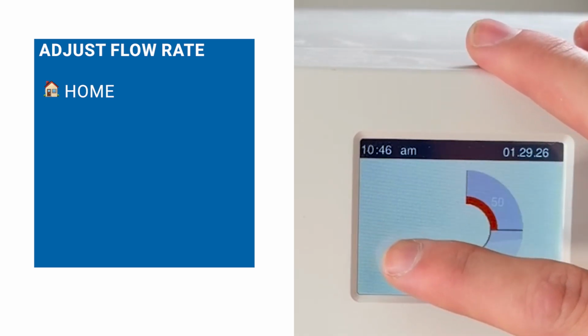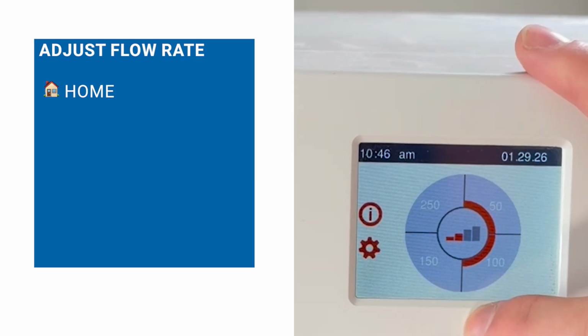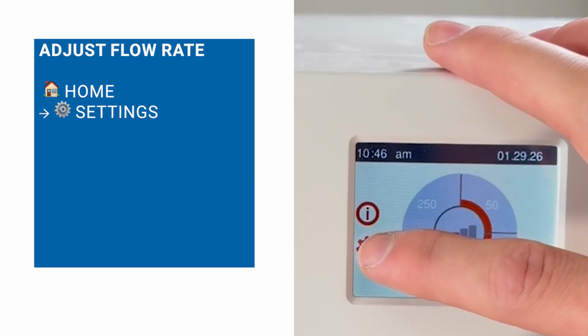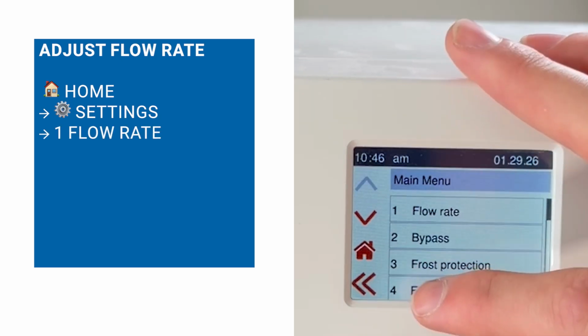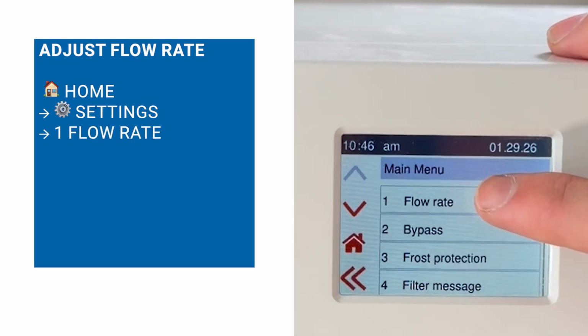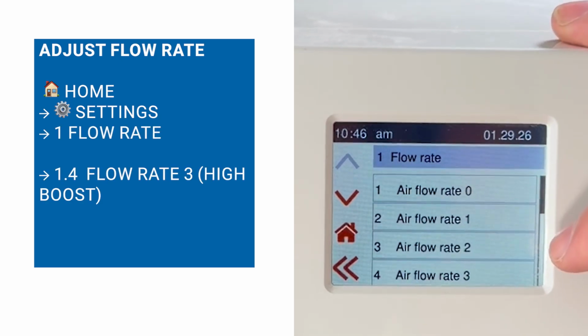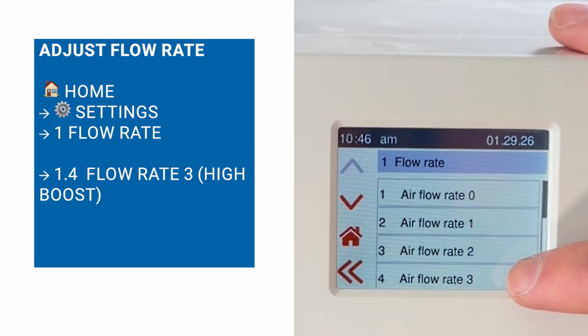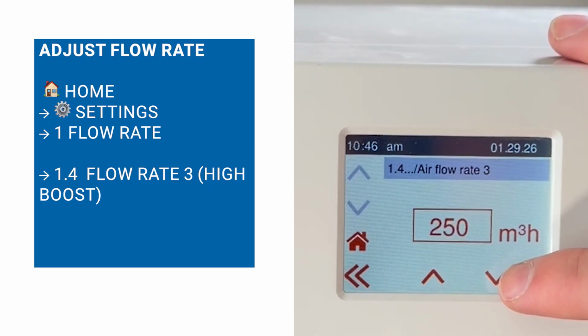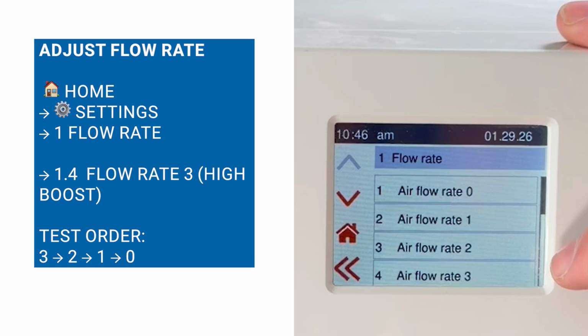For this, hit the Home button to return to start, and then hit the setting menu again, gear symbol. Go to setting 1, flow rate, and start by selecting subsetting 1.4, flow rate 3, or high boost mode. Start with rate 3, then 2, then 1, and then 0. This is suggested as the unit won't let you set a flow rate higher than the setting above it.